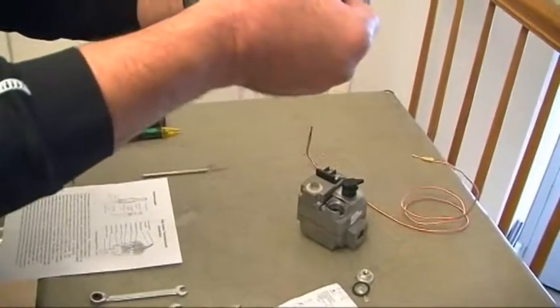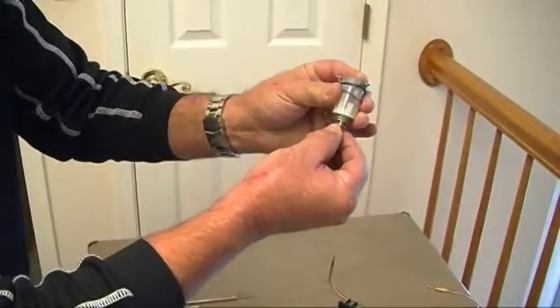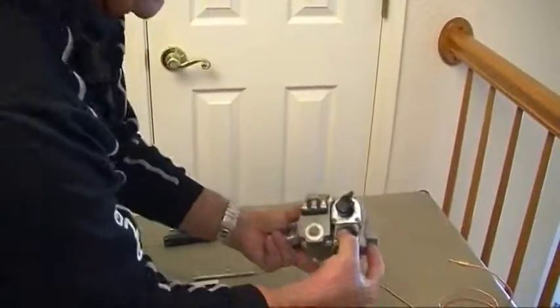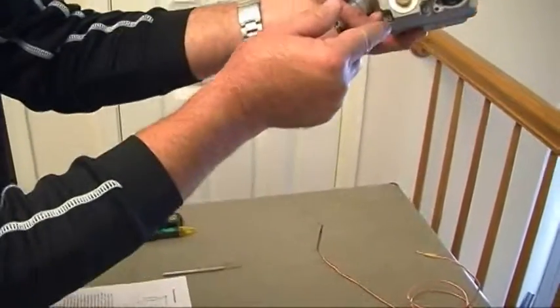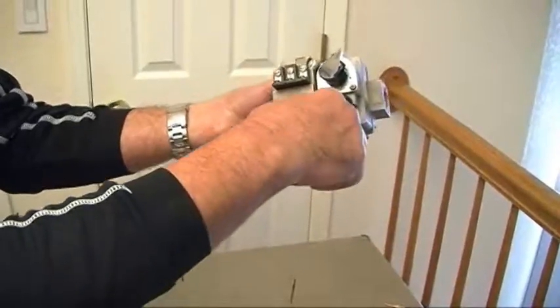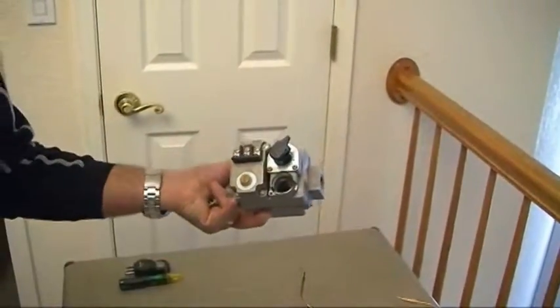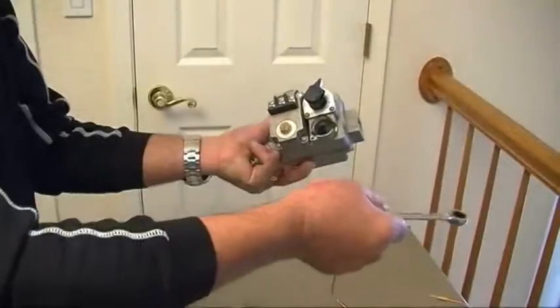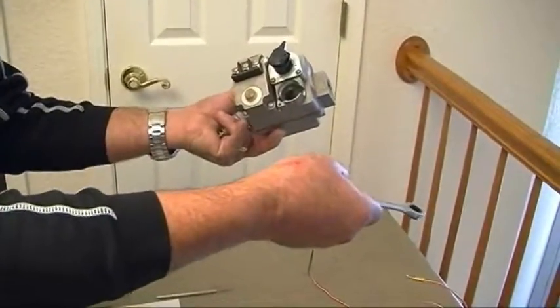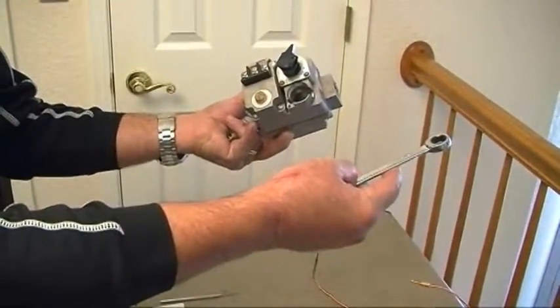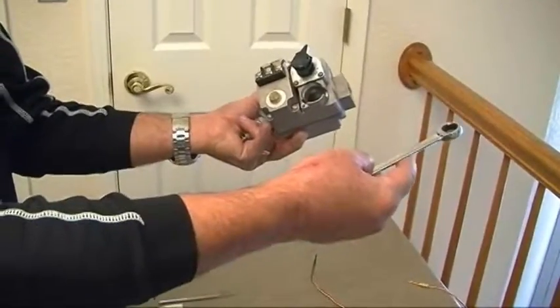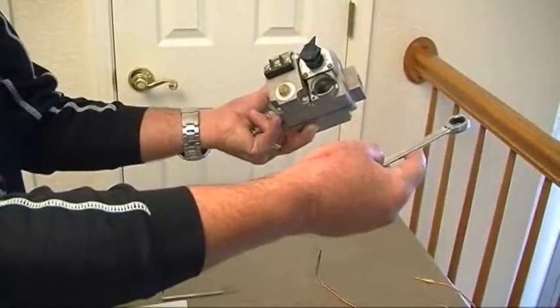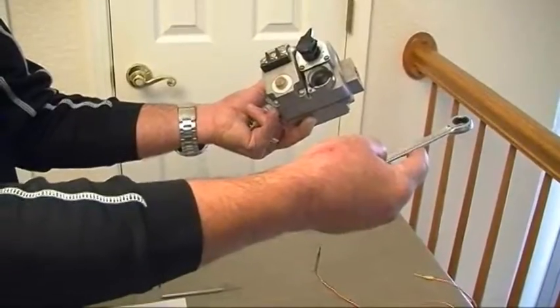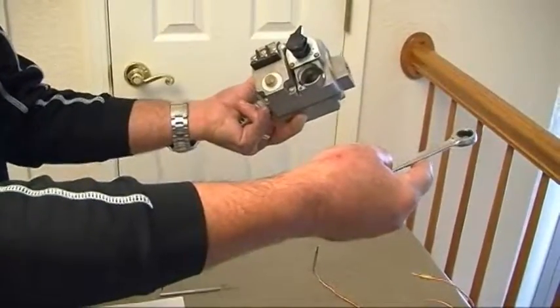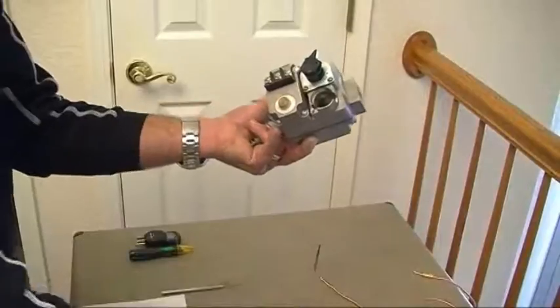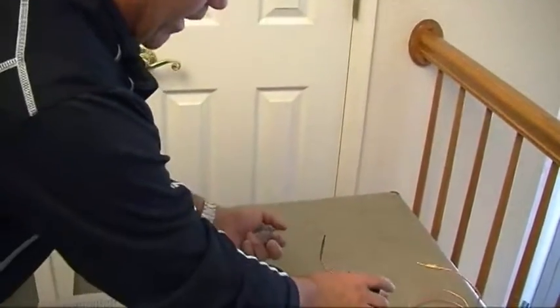Okay, we've removed the electromagnetic power unit, and here is our mainspring. Our mainspring pushes against a lever on the interior, which sits in this position with a rubber cup on the other end, and when it's pushed up, the cup holds the gas from flowing anywhere. When the spring is released and the magnets attract the keeper plate, it drops, allowing flow to the pilot tube. So let's look at that right now.